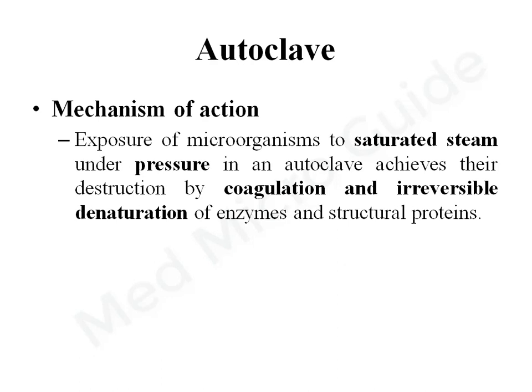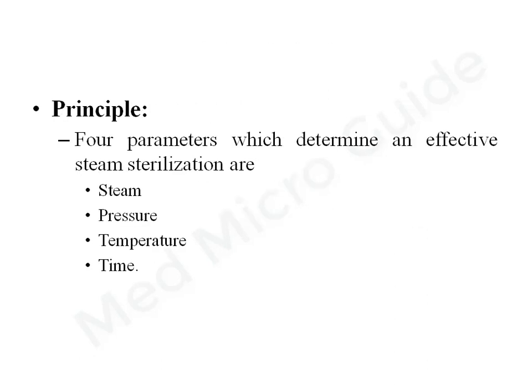The mechanism of action of moist heat above 100 degrees Celsius: when microorganisms are exposed to saturated steam under pressure, they are destroyed by coagulation and irreversible denaturation of enzymes and structural proteins. There are four parameters which determine effective steam sterilization: steam per se, pressure, temperature, and time.